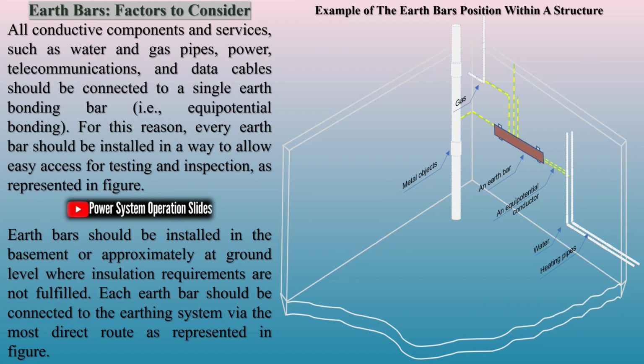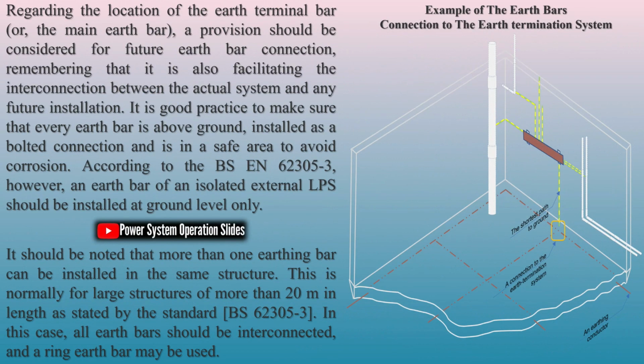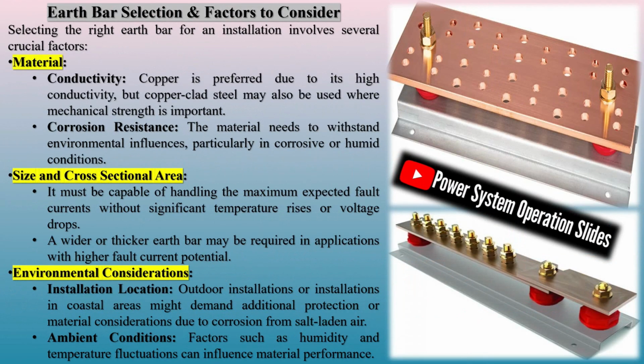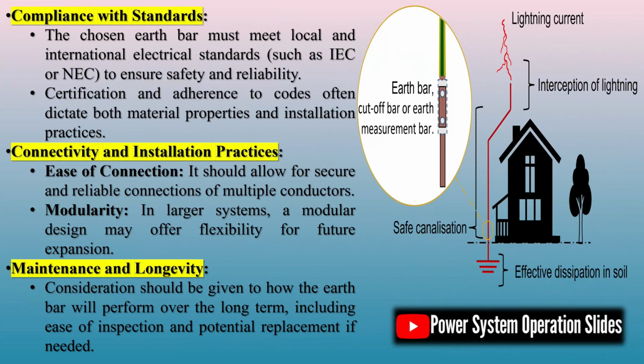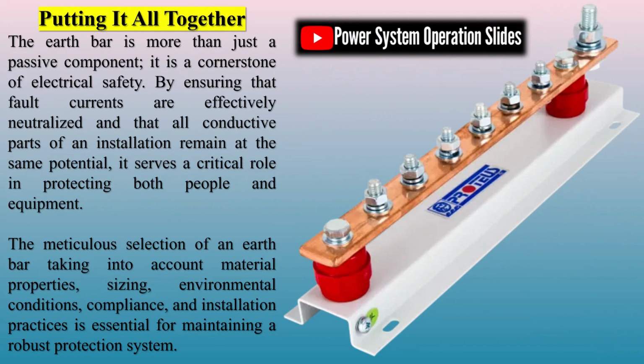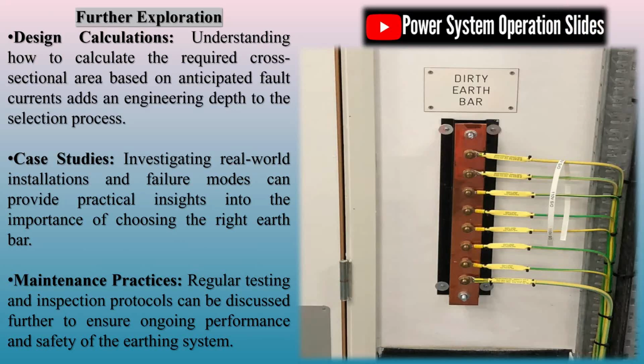An earthing system refers to the collection of components responsible for directing fault currents safely into the ground. A key element in this system is the earth bar, which serves as a common connection point for all conductive components. Beyond its primary function, an earth bar, also known as a cutoff bar, facilitates the disconnection of earthing installations for inspection and measurement purposes. As illustrated in the figure, this component plays a crucial role in evaluating earthing resistance. It is important to note that multiple earth bars can coexist within the same installation, ensuring effective grounding and system reliability. What is an earth bar?